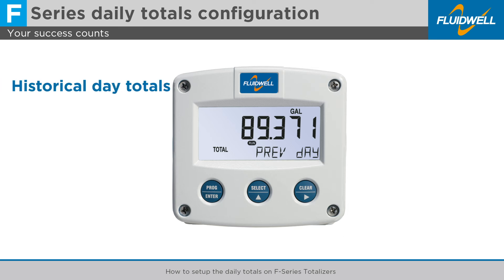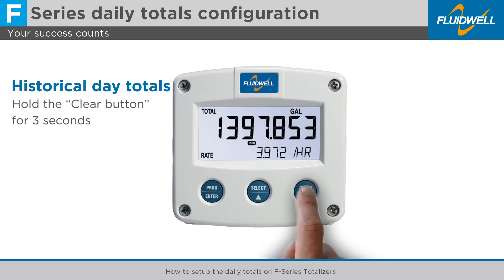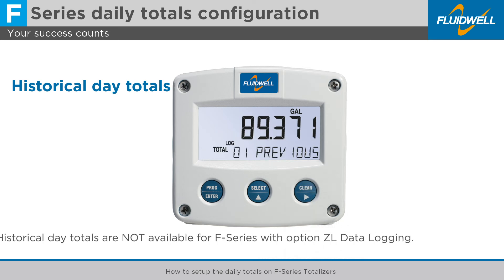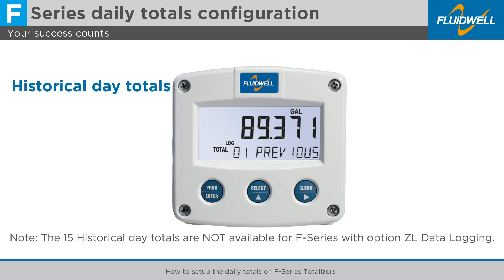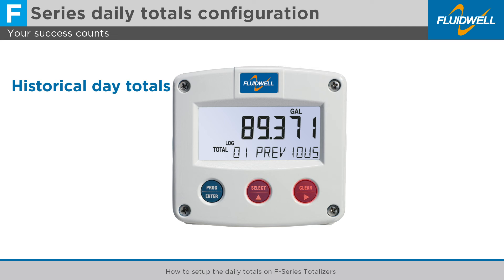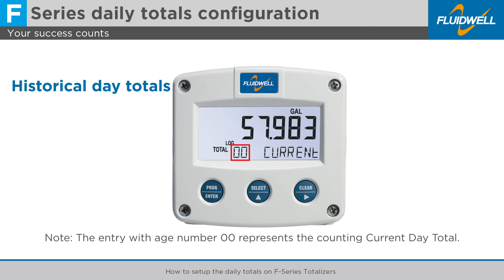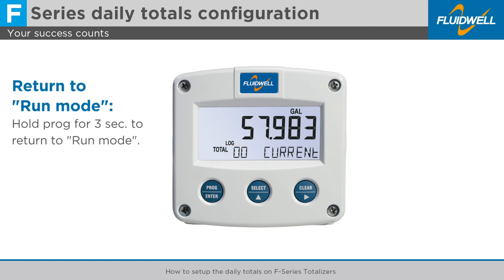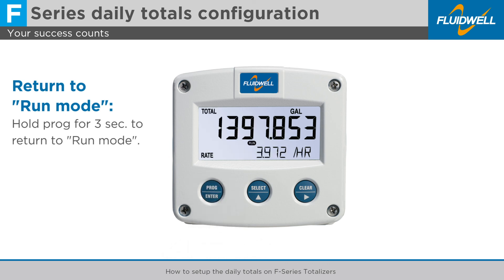To view the historical day totals, hold the clear button for 3 seconds to view the list of 15 historical day totals. Note that the 15 historical day totals are not available for F-Series with option ZL data logging. Use clear and select to scroll up and down through the list. The historical day totals are displayed with a number indicating the age in days. Note that the entry with age number 00 represents the counting current day total. Hold prog for 3 seconds to exit the list and return to run mode.